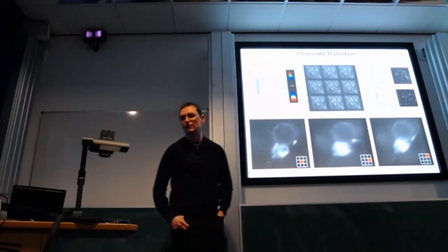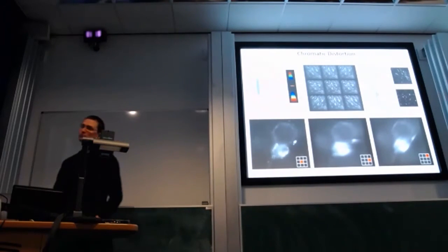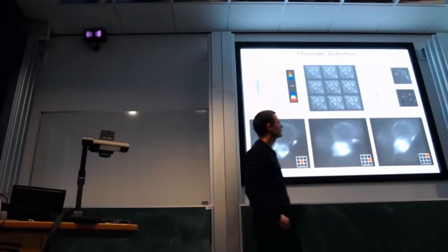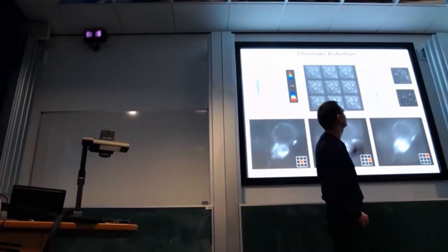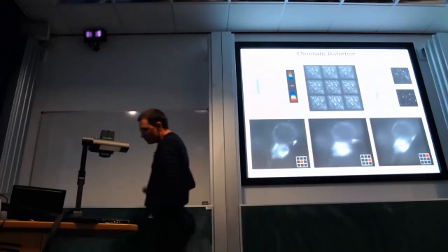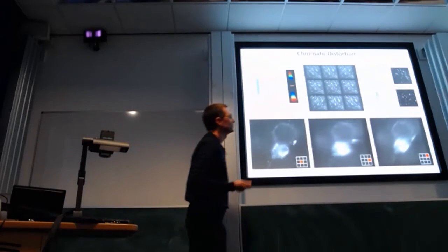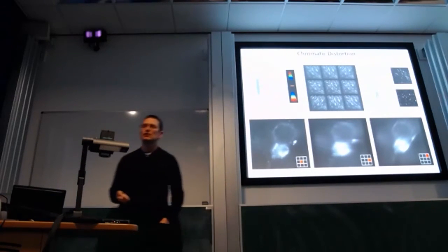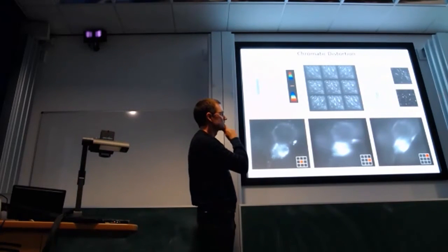There is a huge problem with it, and that is gratings are inherently chromatic. You shine white light in a grating, you get a rainbow. It's pretty, but it's a big problem for us. We're dealing with fluorescence. Fluorophores have a modestly broad bandwidth of emission. And the key point to all of this, the key point to microscopy, is every photon counts. You never want to throw away a point of information, because that's just going to hurt how much information you gather from the system.